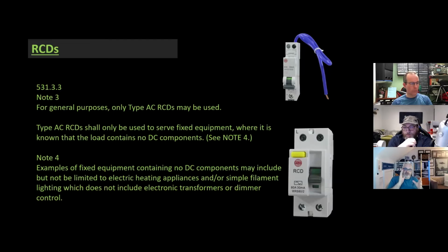By trying to understand this, I genuinely think, and I'll ask it as a comment, can we have an appendix in a future wiring regulations that lists common products and their leakage, so electricians selecting and erecting can make informed protection decisions? Because if we have an installation with 20 milliamp leakage on a circuit, and it's DC and it blinds that RCD, you're better off having a nail in your board, or going back to fuses. Walking away from RCDs and just having cartridge fuses would offer just as much protection. That's the problem.